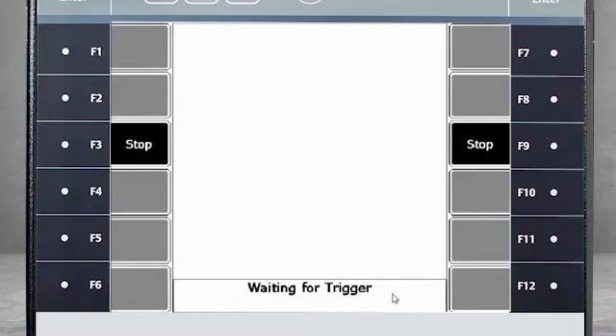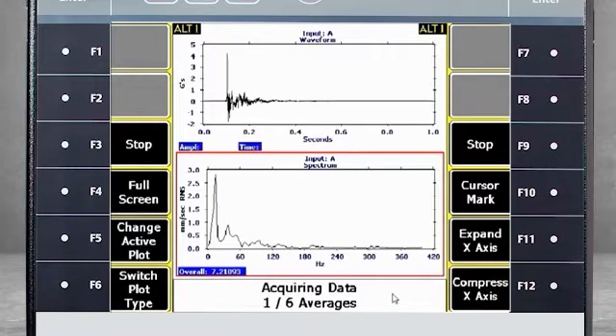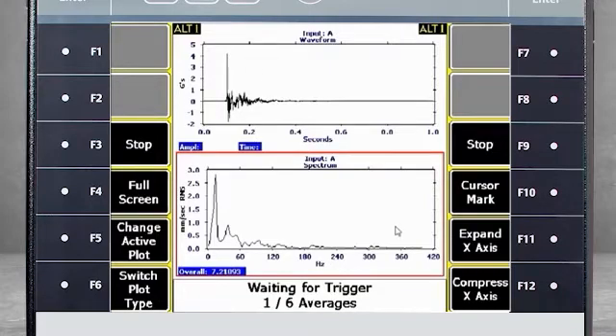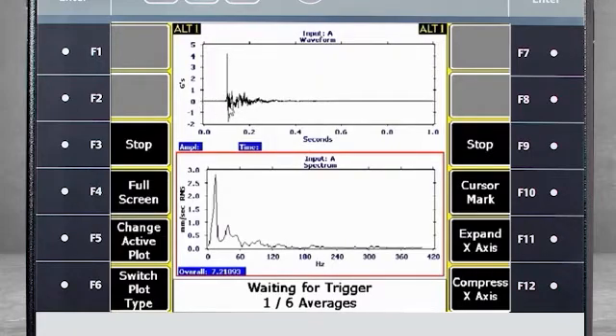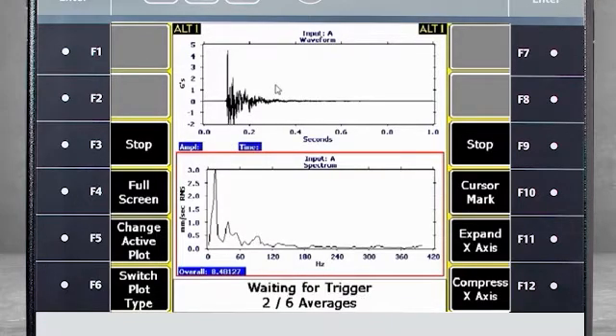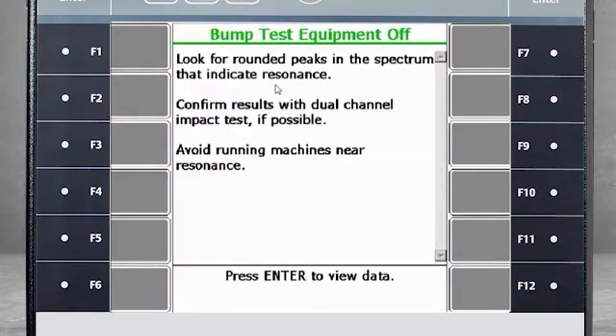I will impact the machine using a rubber hammer. Now you can see on the spectrum that the data from the first impact has been captured. Notice that the analyzer will average six times and is now waiting for the second impact. Before striking the machine again, take a look at this area of the waveform prior to the first impact — this area is called the pre-trigger percentage. Now I will impact the machine another five times to complete the six averages, then press Enter to view the data.